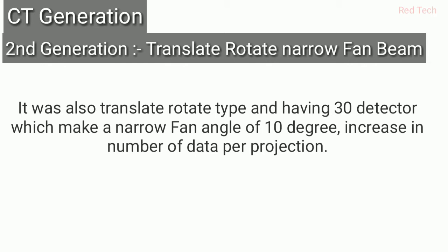In this second generation, the data per projection increases, and because of using 30 detectors and a narrow fan beam, the angle made by the narrow fan beam is about 10 degrees, and it is also called translate rotate narrow fan beam.